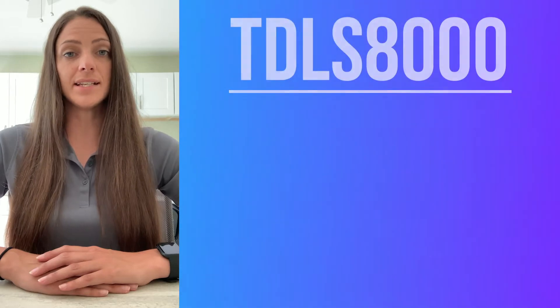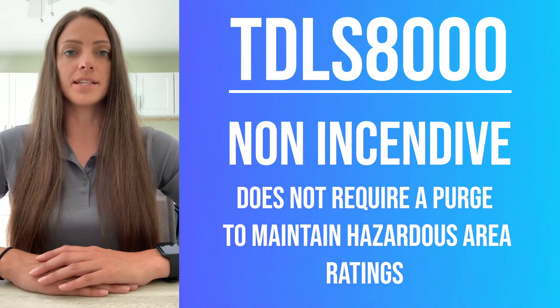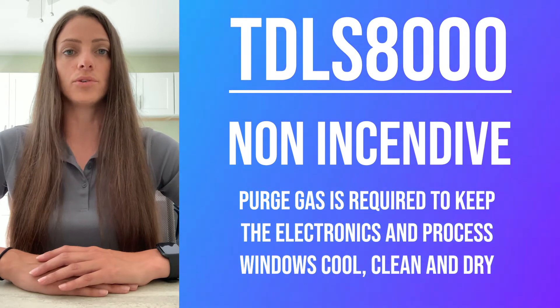The TDLS 8000 series is non-incendive. This means that it does not require a purge to maintain hazardous area ratings. The purge is required to keep the electronics and the process windows cool, clean, and dry.